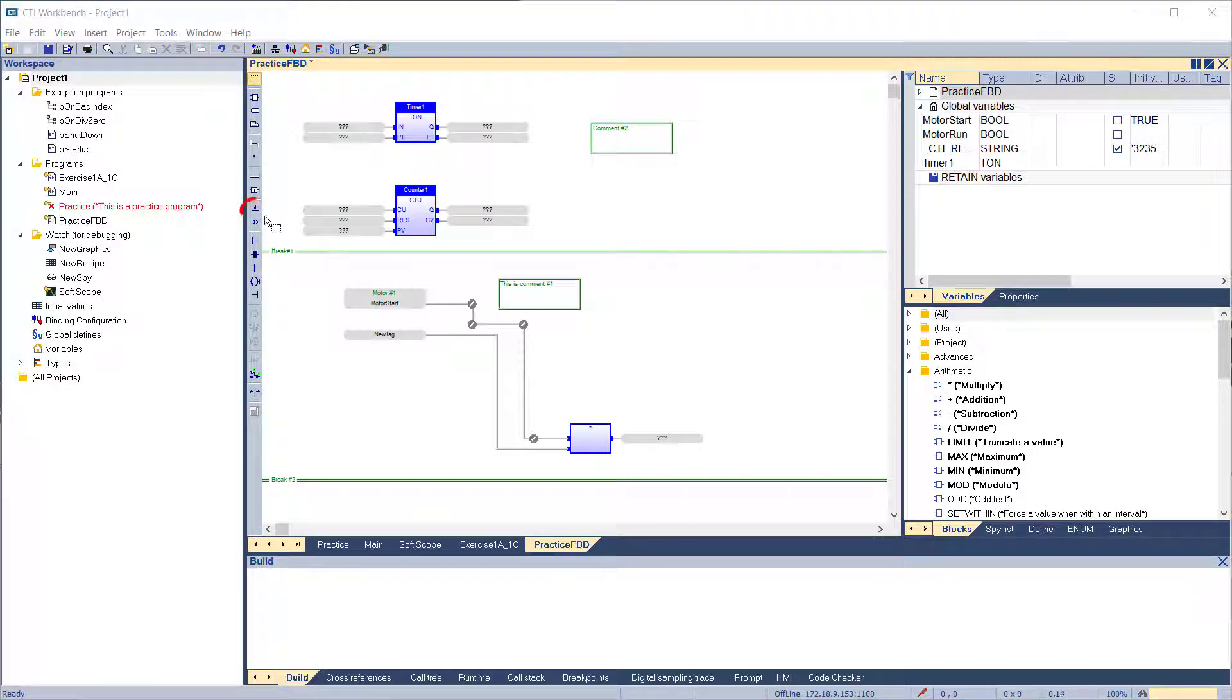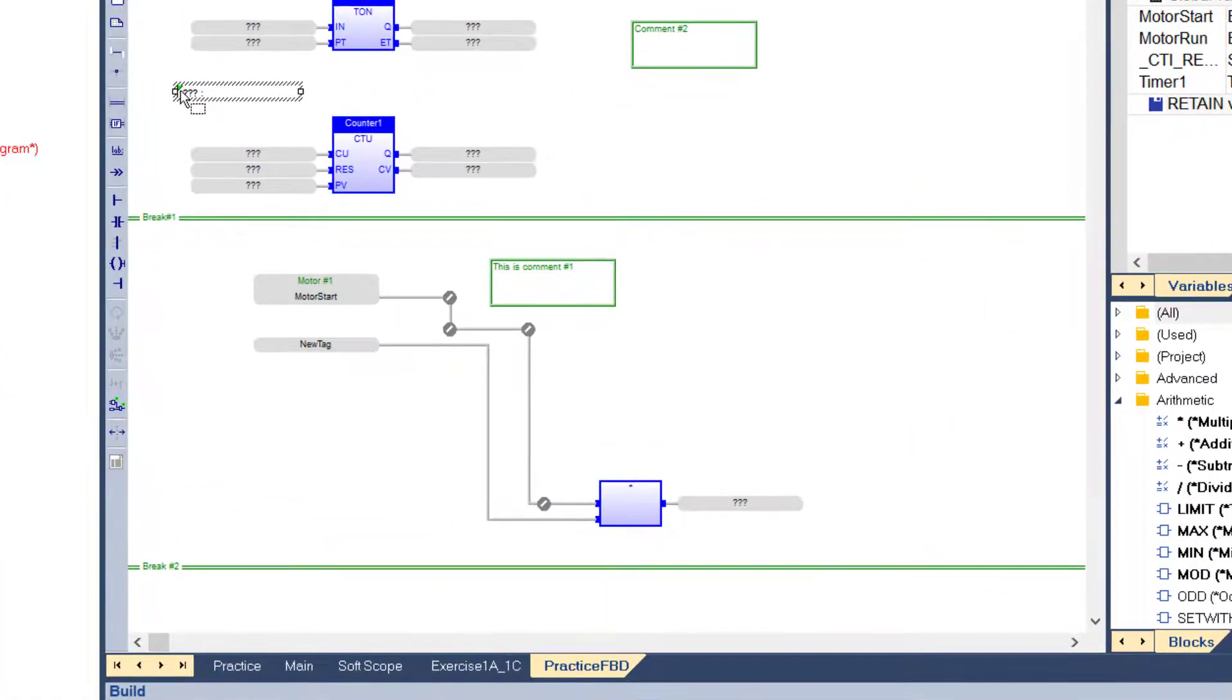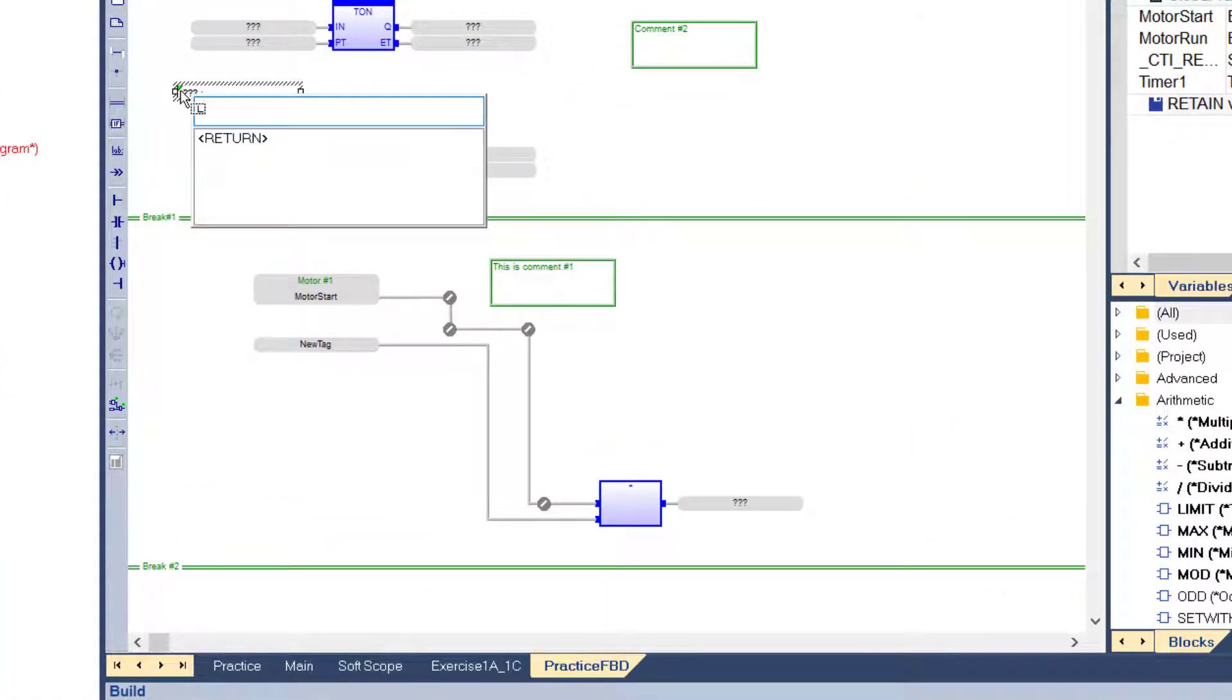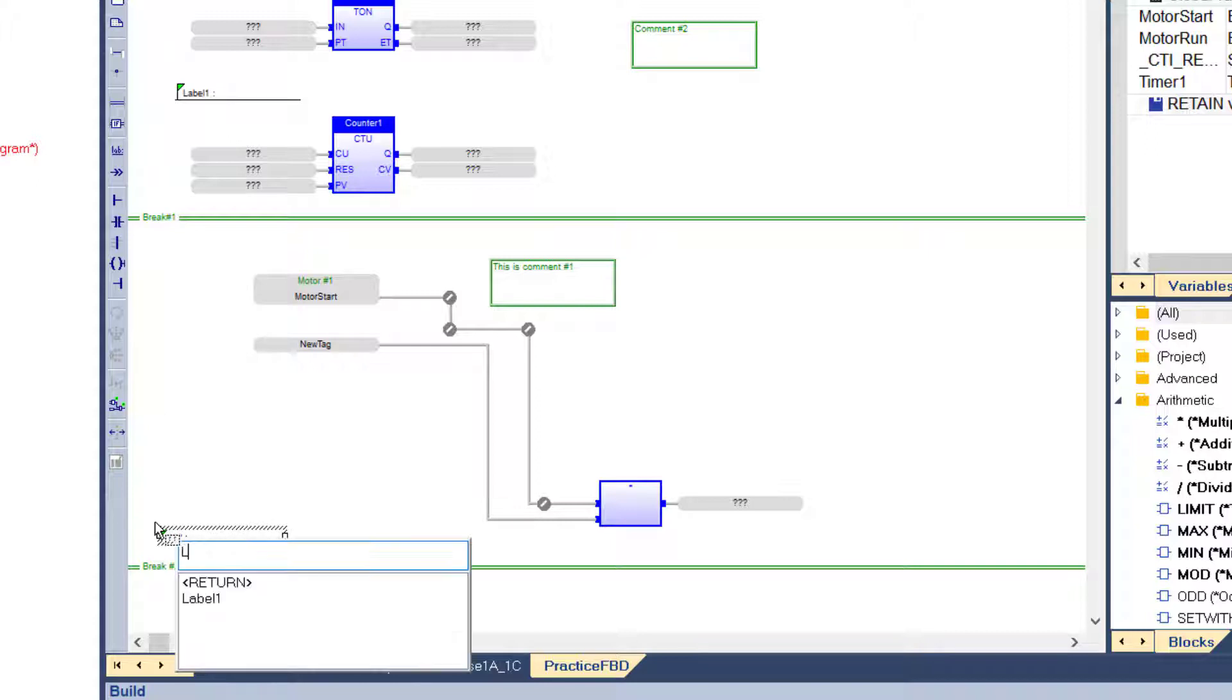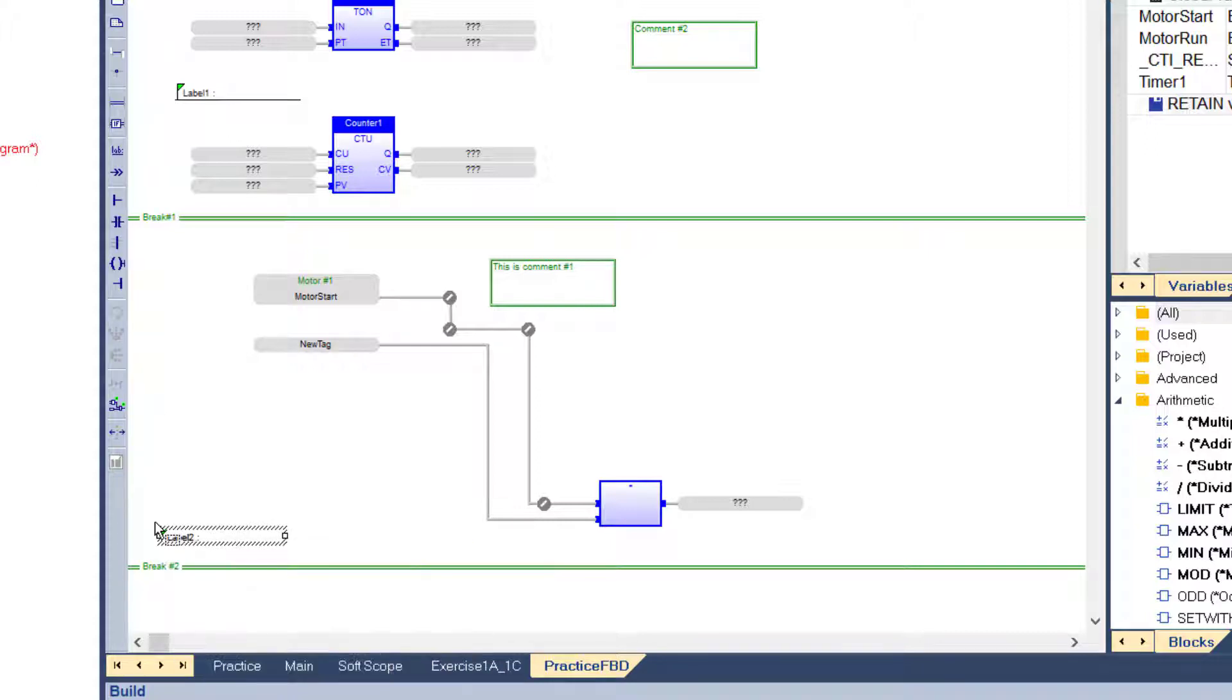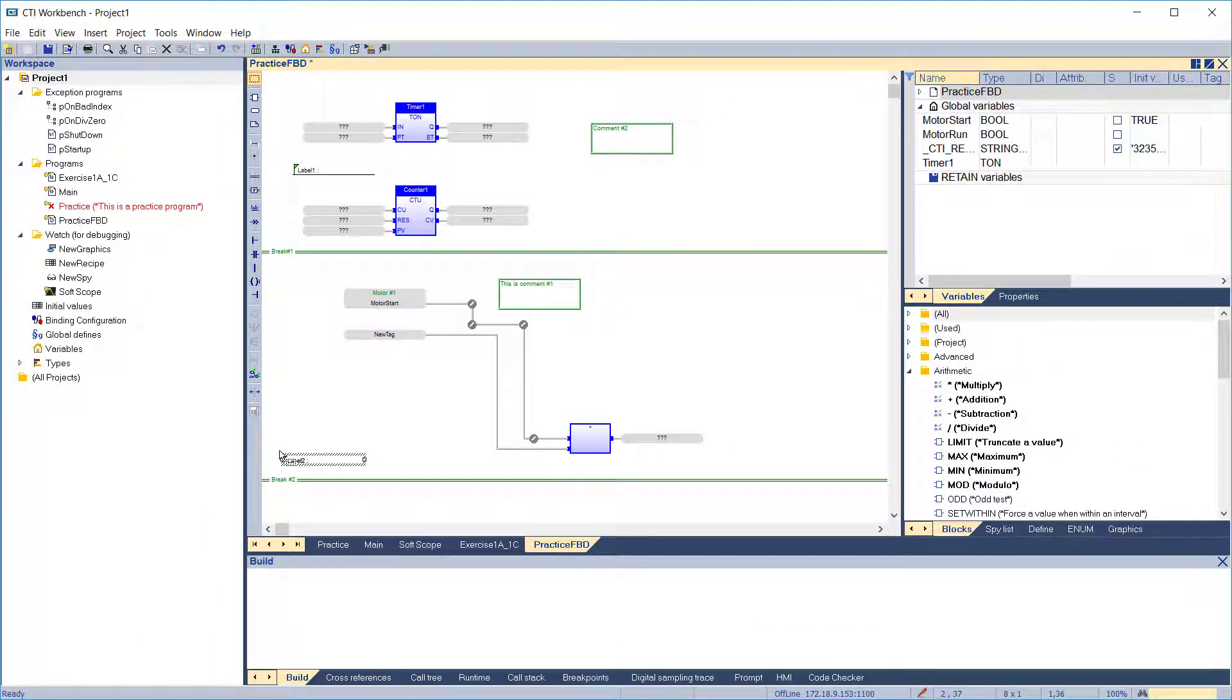Labels are used as a destination of a jump instruction in FBD language. A label consists of a unique name followed by a colon. A label can be inserted anywhere in the diagram and is not connected to any block. A label can also be used for documentation purposes, such as marking parts of programs to improve its readability, without being used as a target of a jump instruction.